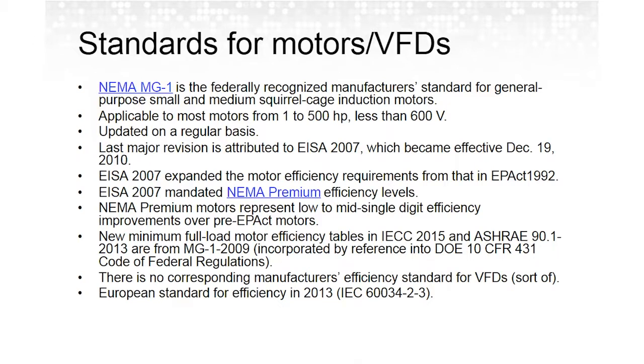And these standards are now incorporated into IECC and ASHRAE 90.1. It really doesn't matter that it's incorporated because these are also mandated on a federal level for the manufacturers. Now, in regards to efficiency standards for VFDs, there is no United States efficiency standard yet. The Air Conditioning, Heating, and Refrigeration Institute, AHRI, does have a standard for the performance rating of variable frequency drives.